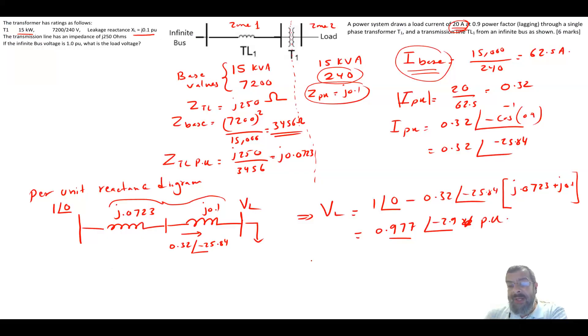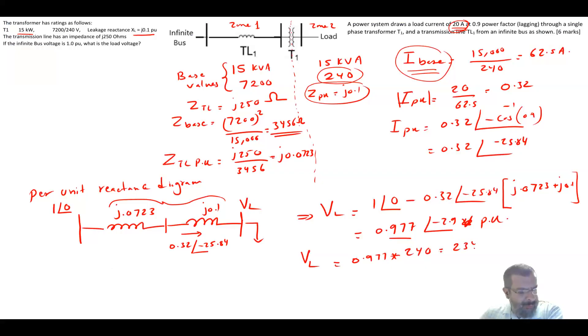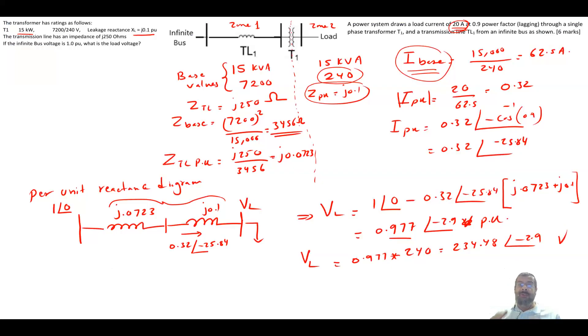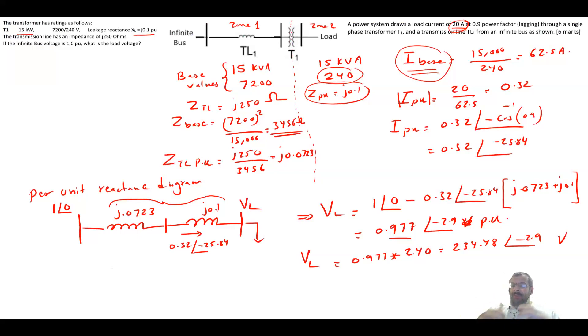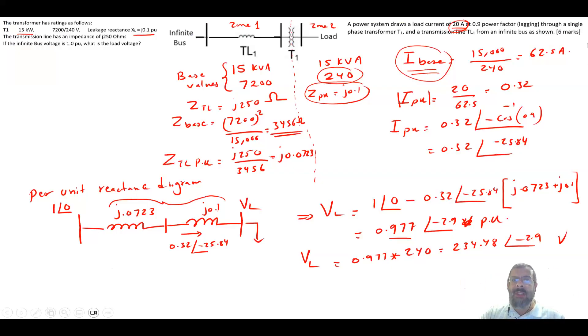To find the actual voltage, multiply the per-unit result by the zone two base voltage of 240 V: V_load = 0.977∠−2.9° × 240 = 234.48∠−2.9° volts. This is an interesting question — more elaborate than typical per-unit problems because it involves a transformer with two different zones.